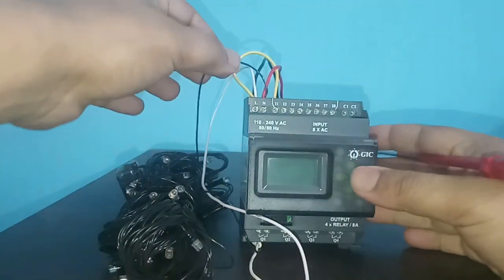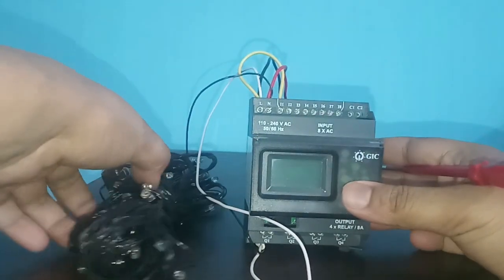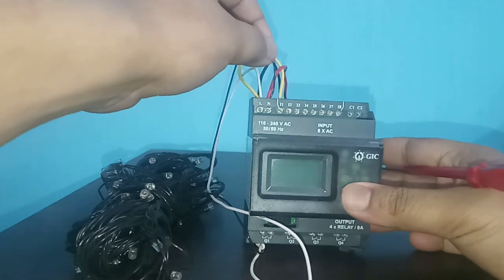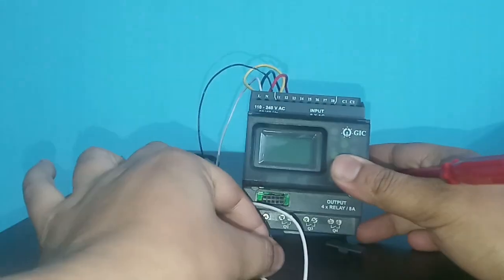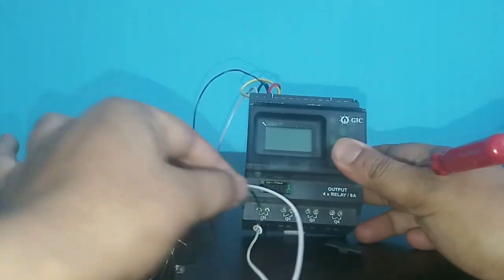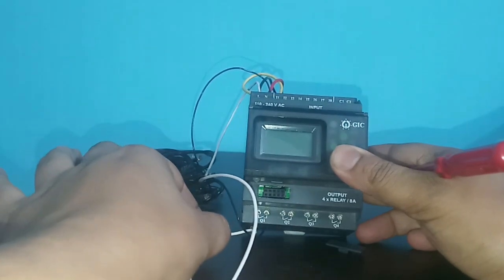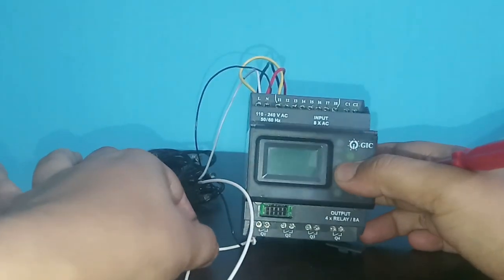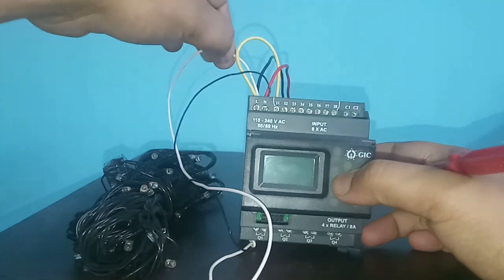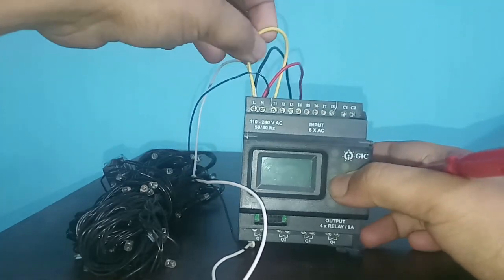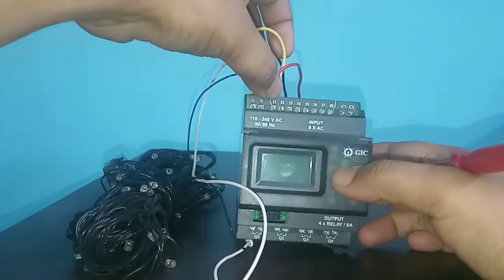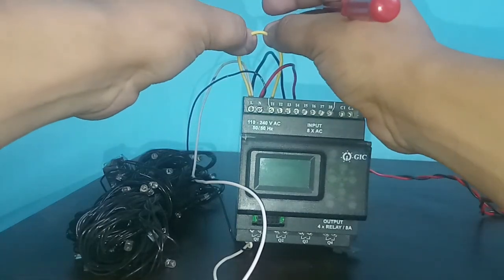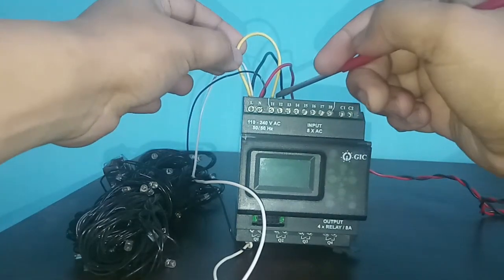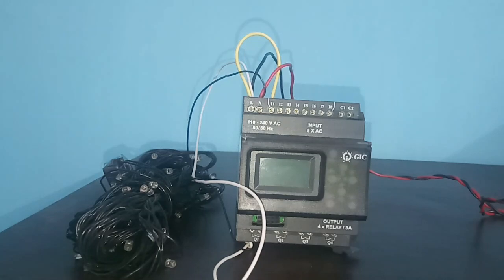Yes, we have connected this small LED light chain with neutral directly, and we have connected the NO side of the Q1 output, and we have connected one phase directly to the common of the Q1 output. And we have connected this phase directly to I1. You can connect any switch in between, so it will control your I1 input here. So let us turn on the PLC.